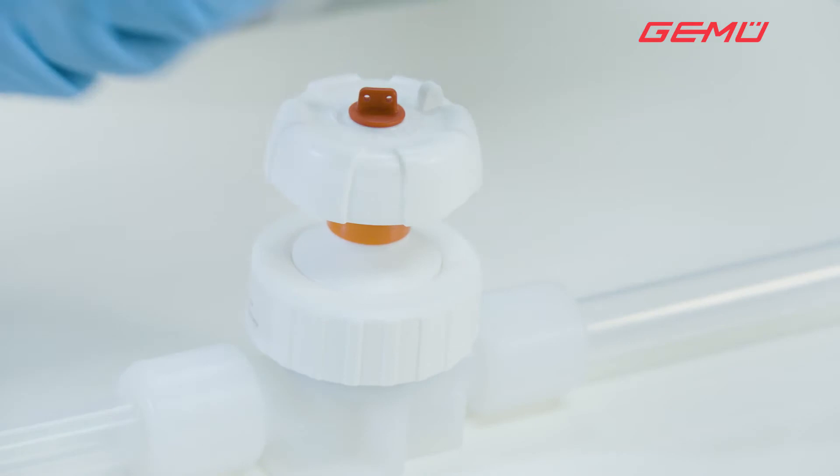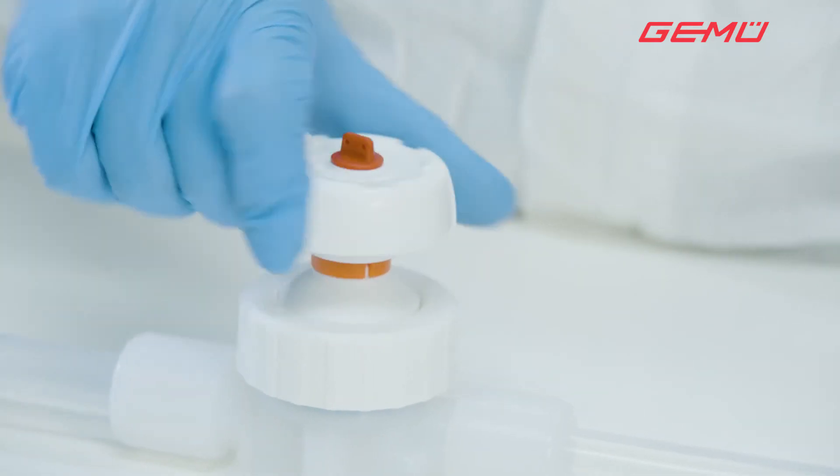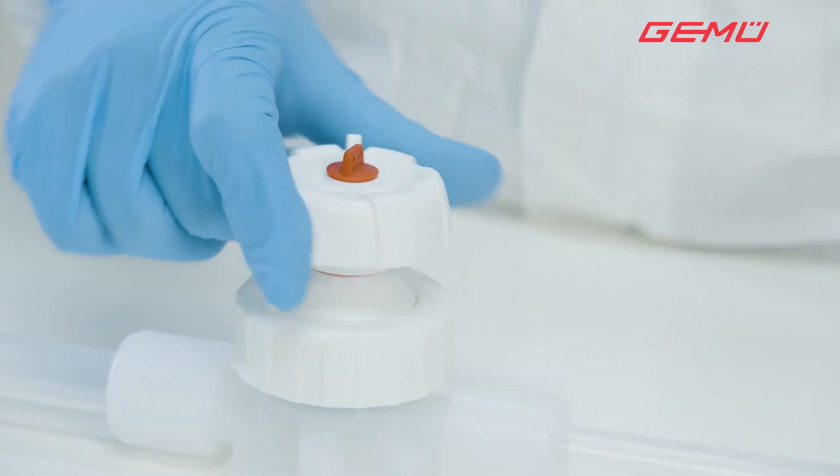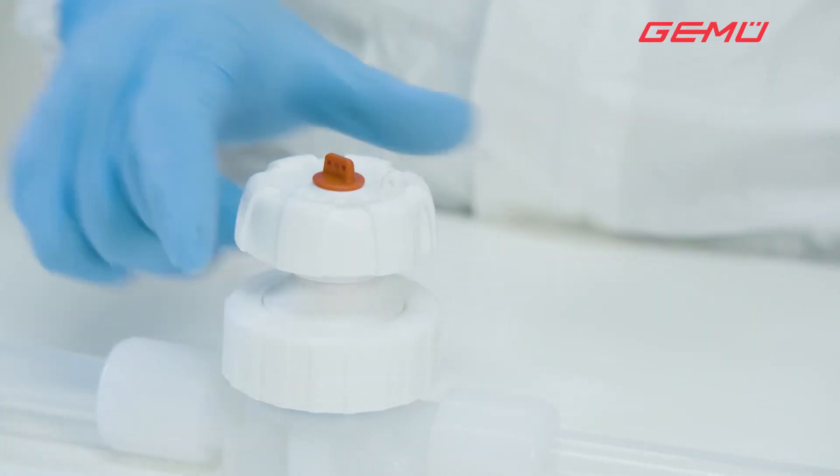Finally move the valve to the closed position. The diaphragm replacement is now complete. Check the valve after one week and retighten the central nut if necessary.